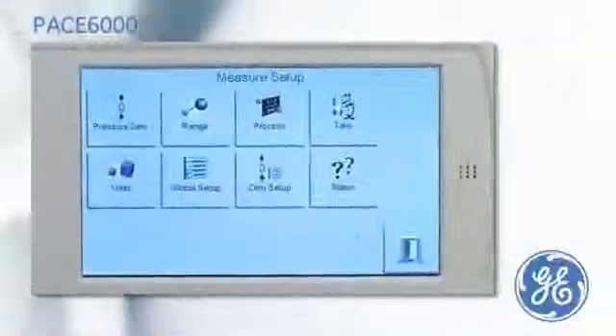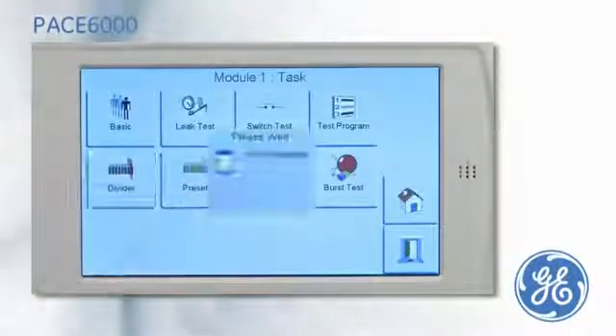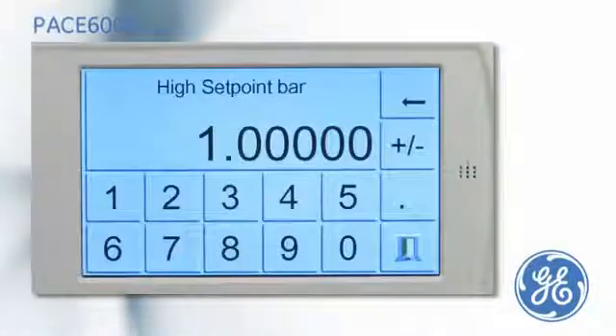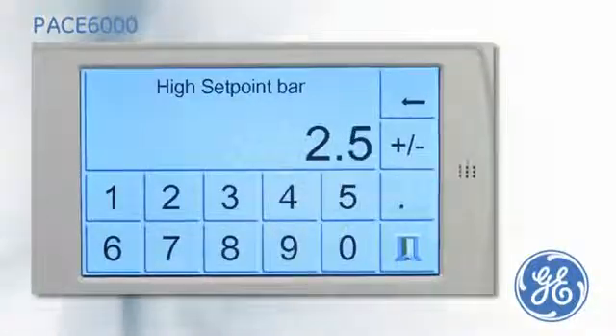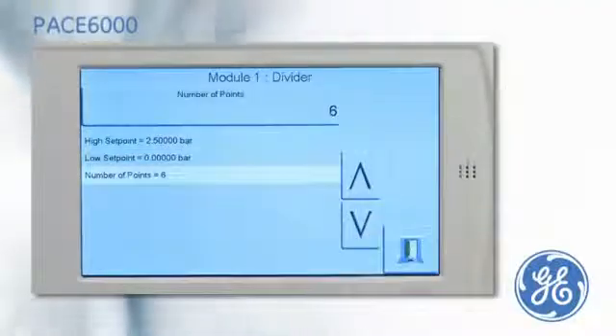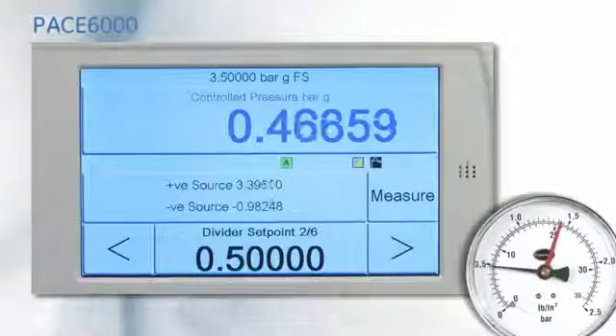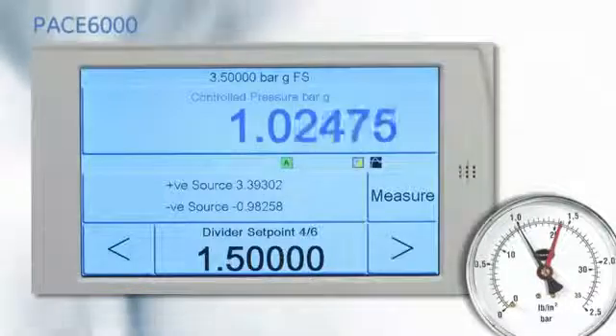An alternative to entering a set point at every cardinal point is to use the divider task. A full scale range of 2.5 bar is entered, the start point is 0, and a number of cardinal points 6. After the PACE has been put into control mode, the pressure can be stepped through the cardinal points by simply pressing the nudge buttons.